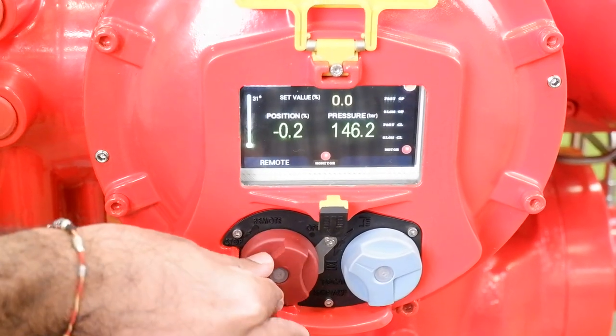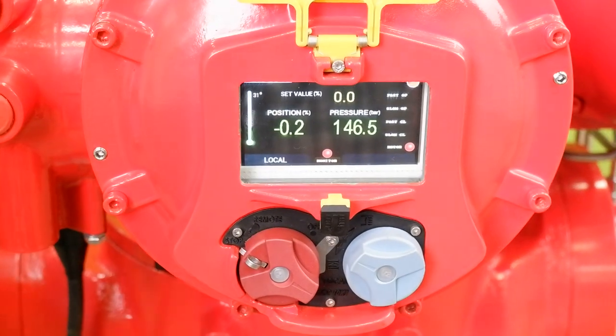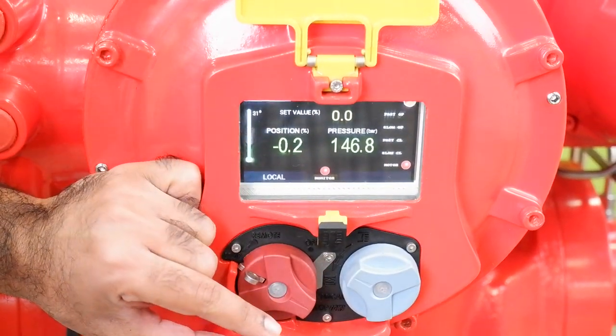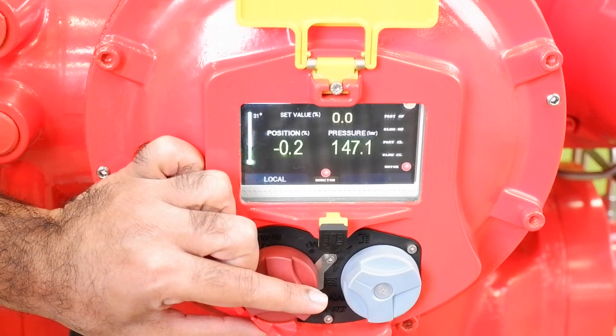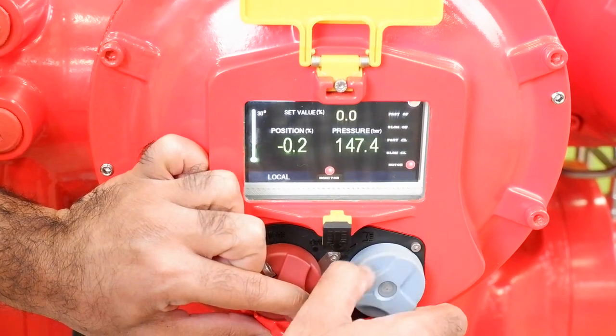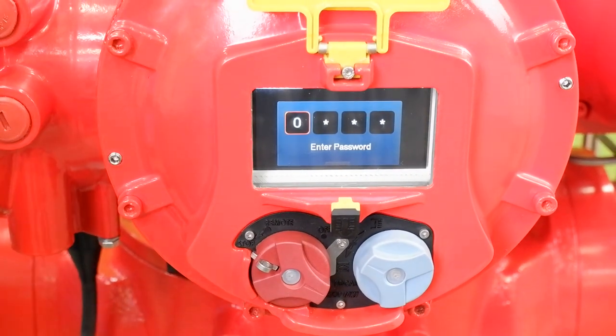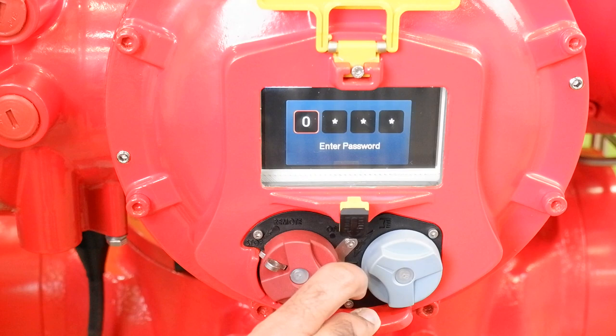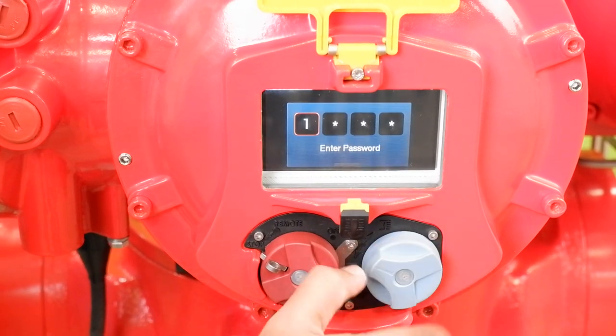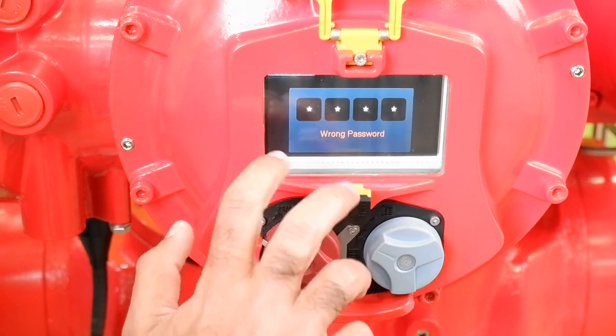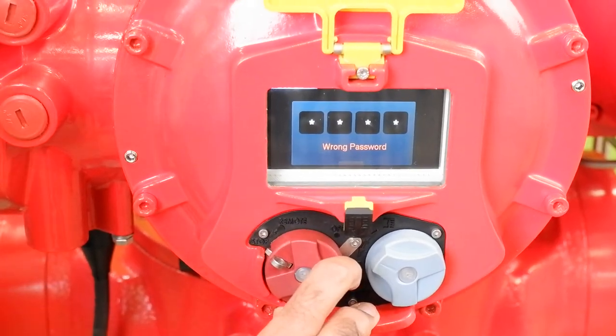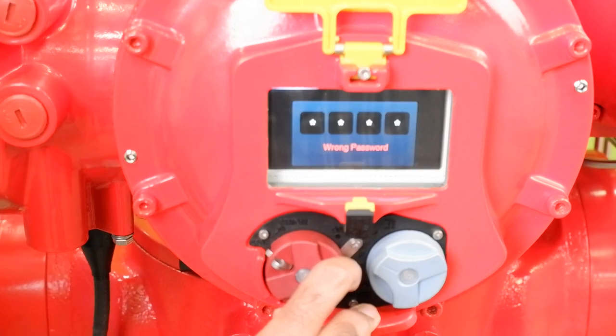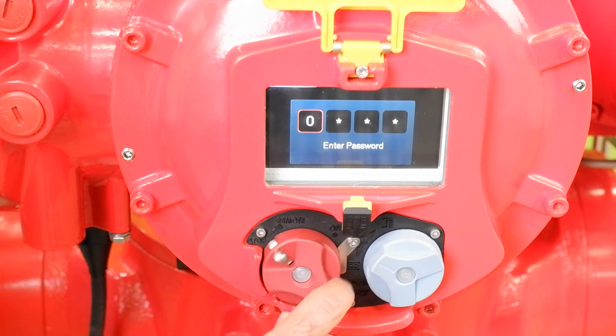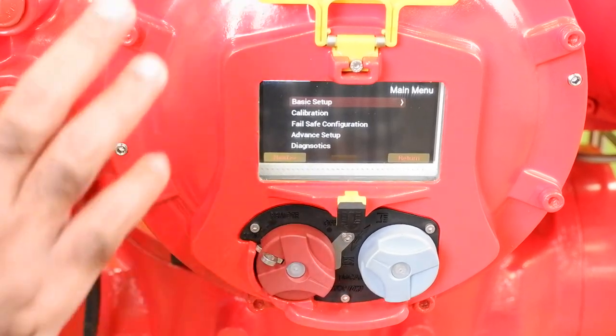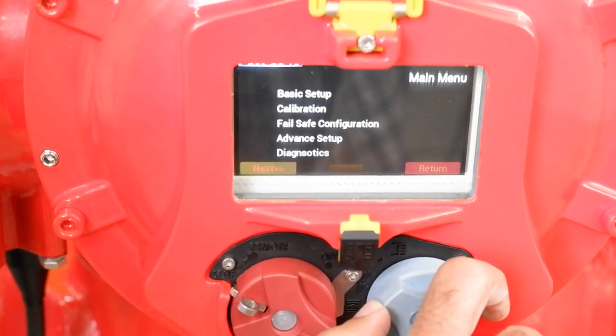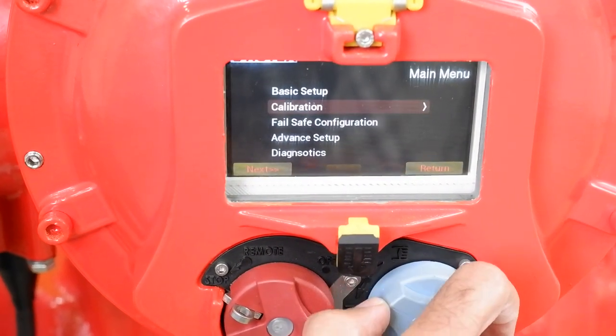Now we will check how to access the menus in this actuator. To go inside the menu, we have to press the red knob downwards and press the blue knob up and down this way. Now you have to enter the password. If you enter the wrong password, it will give you a wrong password message. Here presently the password is 0000, so we'll press the red knob 4 times downwards. The red knob acts as the enter key to go into different sub menus, and the blue knob is for navigating and changing any values inside the parameters.